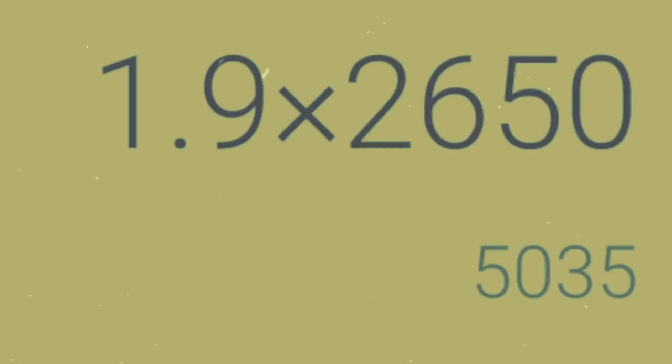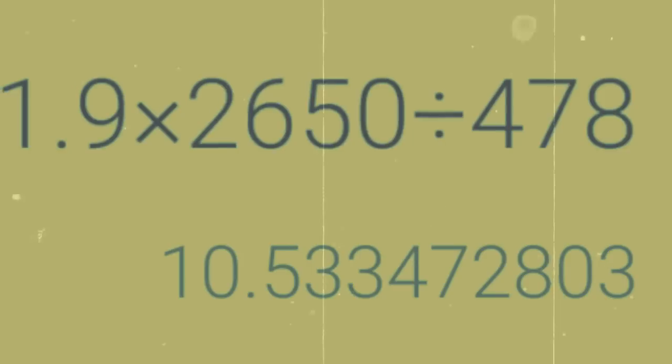So the final step to checking microfarads of a capacitor under load is to take your readings and plug it into the formula I'm about to show you. Our first reading was our amp draw through the start winding, which was 1.9 amps. We're going to multiply that by a constant of 2650. Our next reading was our voltage, which is our back EMF of the motor across the capacitor. We're going to divide that by that number, which was 478. We're going to equal that out to 10.5 microfarads under load. Now most run capacitors in the HVAC industry have stamped right on it, plus or minus 6%. So we are in the safe range with a 10.5 calculation of our microfarads under load.